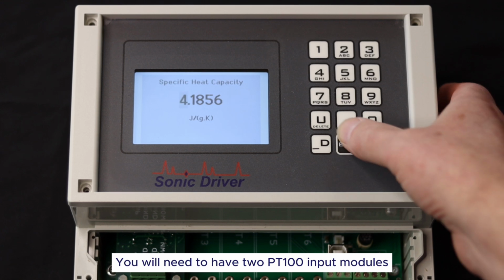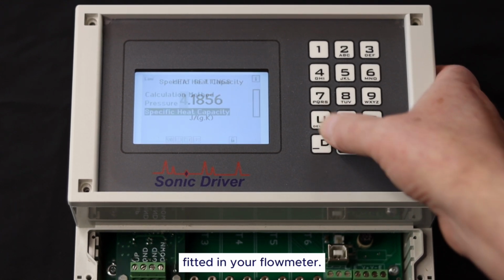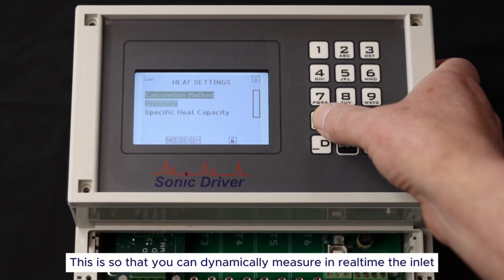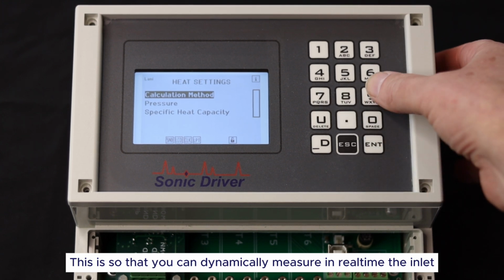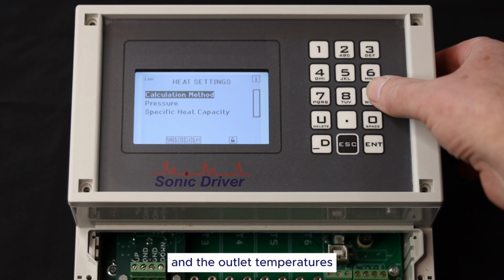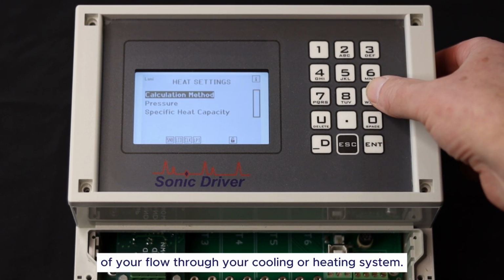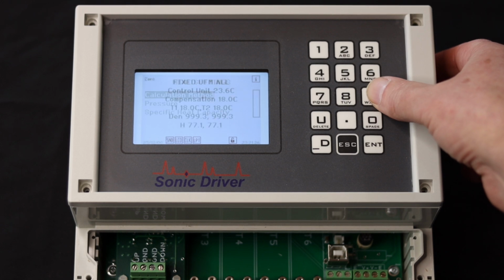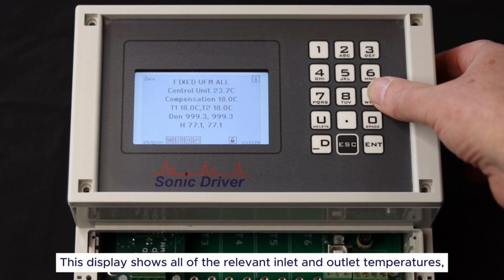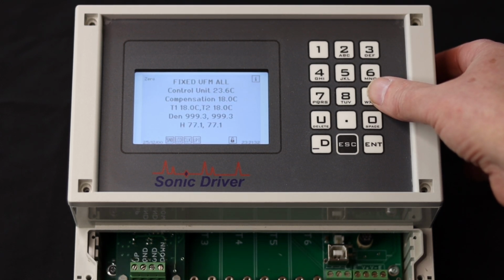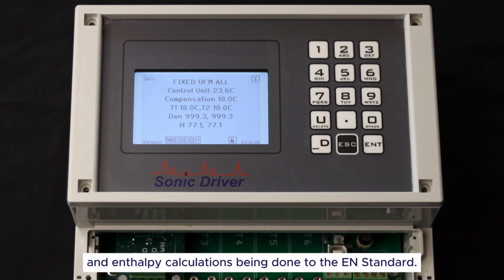You will need to have two PT100 input modules fitted in your Flowmeter. This is so that you can dynamically measure in real time the inlet and the outlet temperatures of your flow through your cooling or heating system. This display shows all of the relevant inlet and outlet temperatures, liquid density, and enthalpy calculations being done to the EN standard.